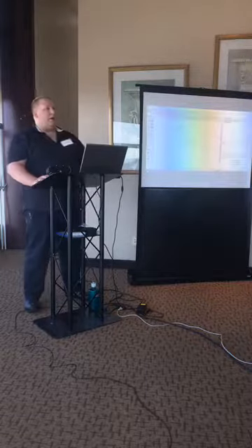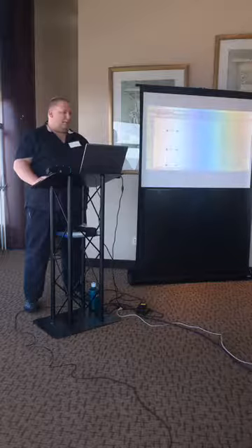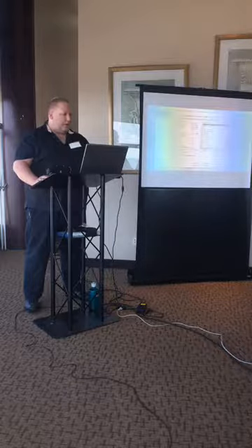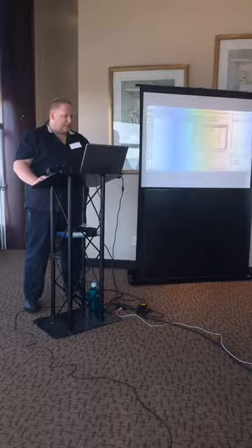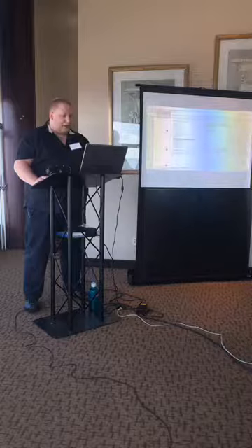Okay, so when I run the model, I'm going to look for the pipe size that gets me below 6 feet per second for the velocity. So I'm going to go to my output control window and set up some custom output here. I'm going to remove the name of the pipe, put velocity above flow rate, and add nominal pipe size to the list. I'm going to move that all the way up to the top. There we go.